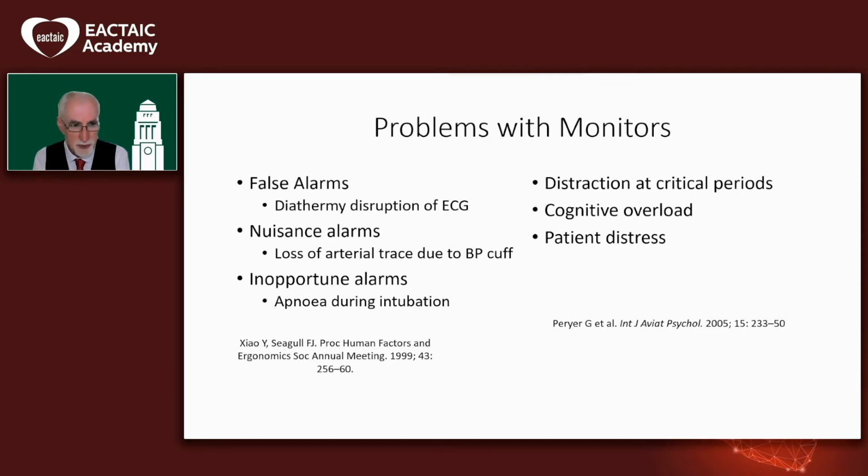The false alarms, for example, caused by diathermy disrupting the ECG. Nuisance alarms, for example, the loss of an arterial trace simply because the BP cuff has gone up or because we're taking an arterial blood gas sample. Or alarms that don't really add anything to care, the apnea alarm going off during intubation.